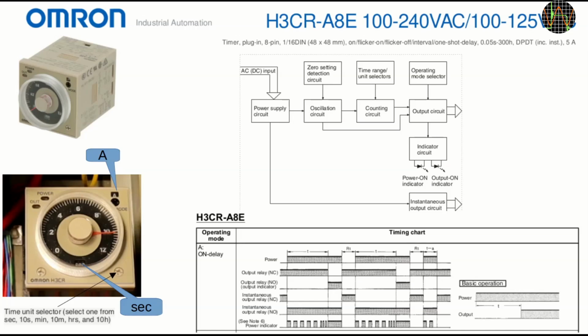The other 4 modes supported are complex and really not important here. Mode A basically means that the instantaneous contact is activated immediately and the other contact after the elapsed time t, and then stays activated until the power to the timer is removed. The point of all this is that the timer needs to be activated, and since there isn't a button on the front that does this, I suspect it's the strange 3-pin connector on the back.